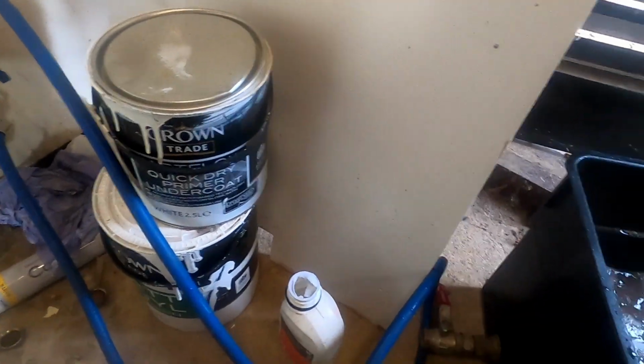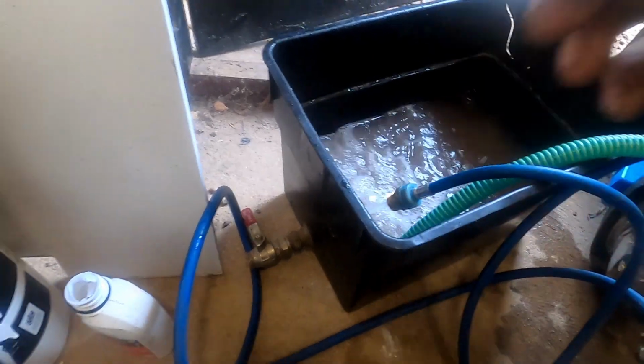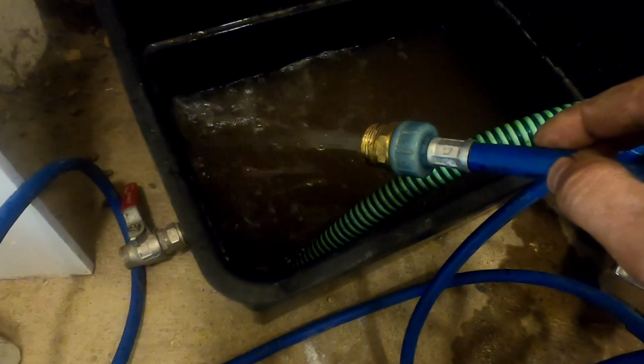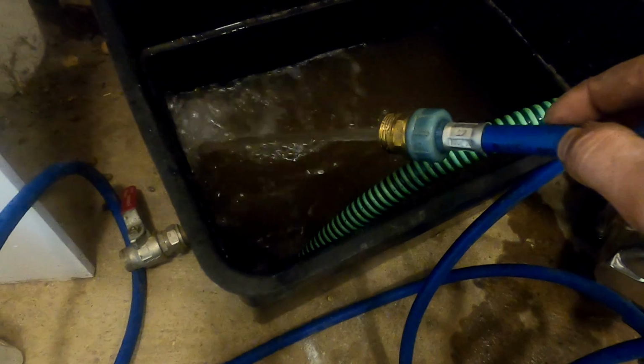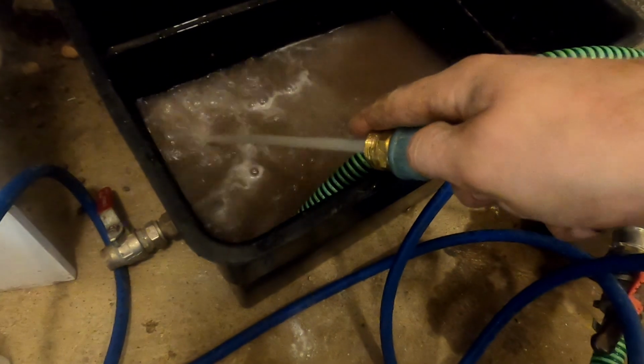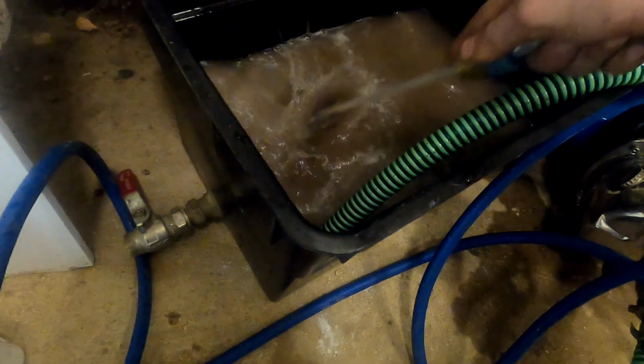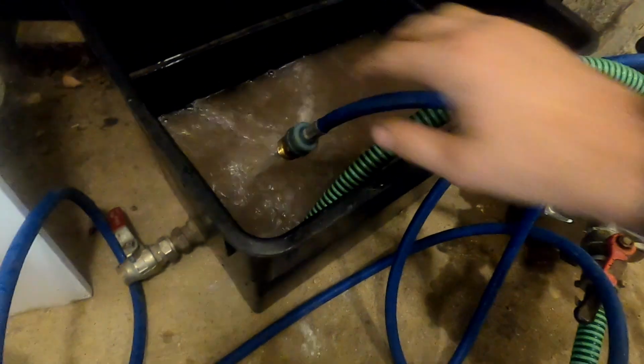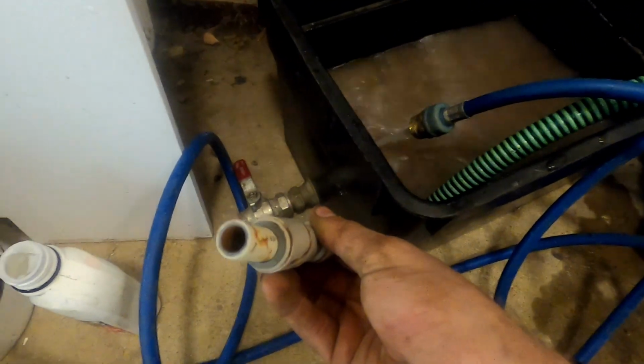So you should see that one come all aerated. So you'll see that coughing, that's all the air in the circuit that we don't want. So we'll just wait for that to clear. So the water looks a little bit manky inside. It's no surprise because it's obviously been topped up from the start. It looks pretty clear coming back, but inside the pipe that I cut out looked red, so I might flush these circuits out as well.